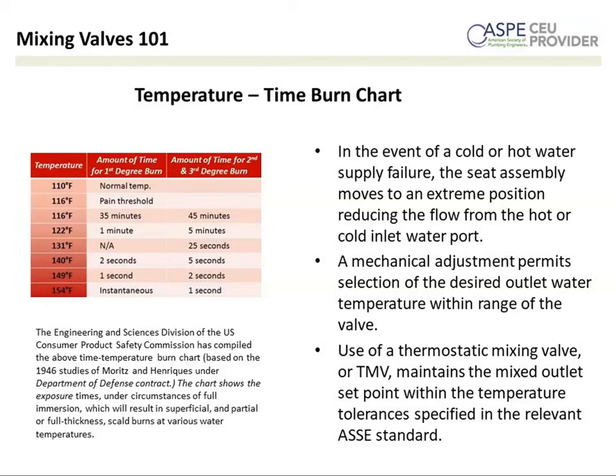So there's a question that came in: what heat source is sufficient to use with digital mixing? Can standard water heaters be used, or will boilers have to be used? So listen, both. Typically we use digital mixing with tanks, with instantaneous, with boilers. We've used them in numerous different applications with numerous different heat sources.